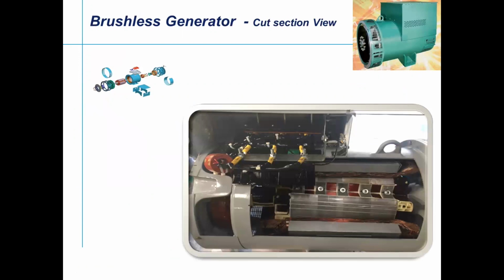So I just want to give a small touch on what we have seen in the previous one. And this is a cut section of our generator. You can see a rotor winding and the stator winding here. This is a terminal box. From that, the lead wire is taken to the termination. And this is our exciter stator and exciter rotor. And of course, very important, though it looks very small, it's a QDC, quadrature droop CT, which is used for parallel operation. So this is a cut section of the generator, what we are seeing across the system.